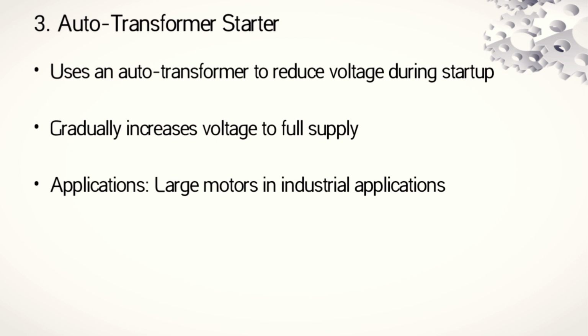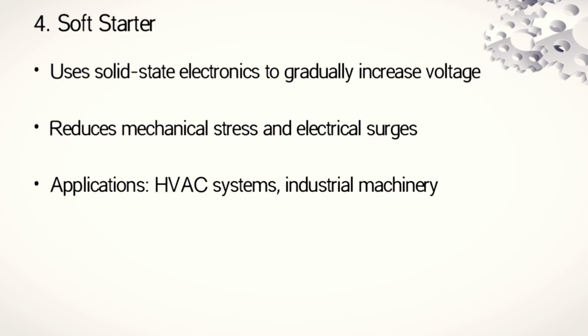Having known that, we can say that the auto transformer starter uses an auto transformer to reduce voltage during startup. That means that the transformer in question is a step-down transformer. So it gradually increases the voltage to full supply, and the auto transformer starter is used in large motors in industrial applications. The fourth one is the soft starter. The soft starter uses solid state electronics to gradually increase voltage. Again, it reduces mechanical stress and electrical surges. Applications of the soft starter method are HVAC systems and industrial machinery.